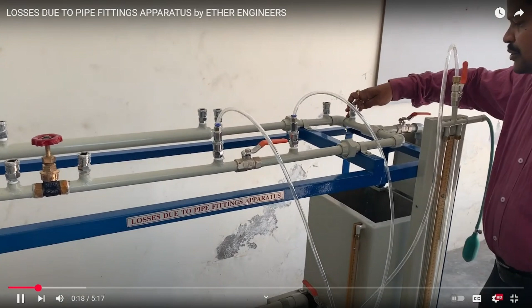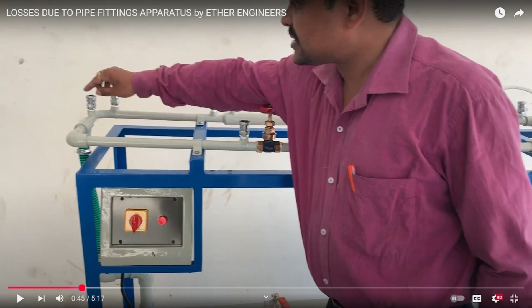For the manometric connections, for different velocities, different flow rates, we will note down the pressure drop. And from that pressure drop we will back calculate the equivalent length for that particular fitting and compute the pressure drop, right?